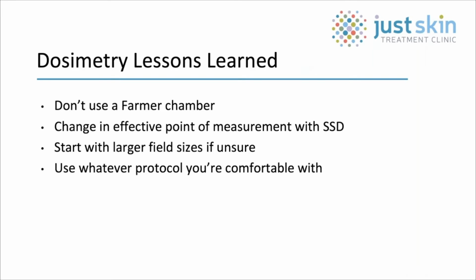There are several lessons I learned through this process, and hopefully I can save you some time and hassle. Firstly, don't bother using a Farmer chamber. I had mine calibrated down to 10 kV, and the calibrations lab told me not to use it because it would be inaccurate, which I have experimentally validated by getting unusable results. If you're unsure about your measurements, start with the largest field size. This will be more forgiving to setup and calculation errors. It will also be the main field size you use when treating patients. You can see that each dosimetry protocol delivers similar results, so use whichever one you're comfortable with or have the equipment for.